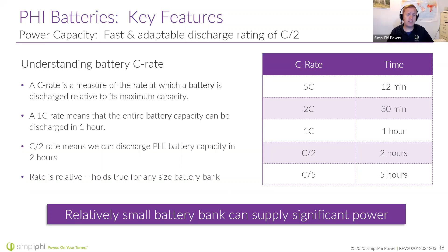As you add batteries to a system, an older system, a lot of our competitors won't allow you to expand a system. So these are two great features right here: one is scalability, one's expandability. Scalability, what I mean by that is that you can scale up our batteries to make the system size that you need. You can keep parallel wiring up the batteries. There's no communication lines to run. And as you scale up those batteries, you're scaling not only in energy storage capacity, but also in power throughput.